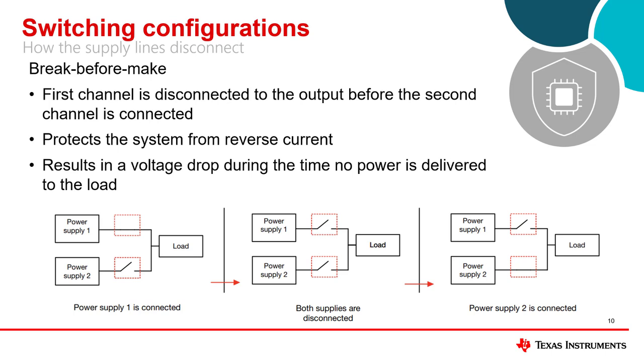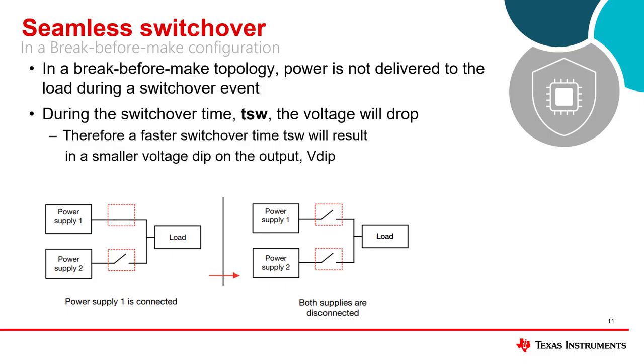In the break-before-make configuration, the first channel is disconnected from the output before the second channel is connected, as shown in the figure. This protects the system from reverse current; however, it does result in an output voltage drop during the time no power is delivered to the load. In the preferred break-before-make topology, it's important to consider the implications of the time where no input is connected to the load during a switchover event, during which the voltage will drop.